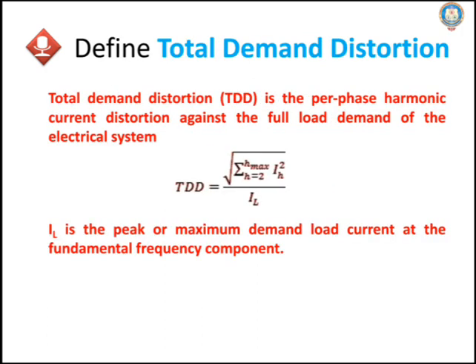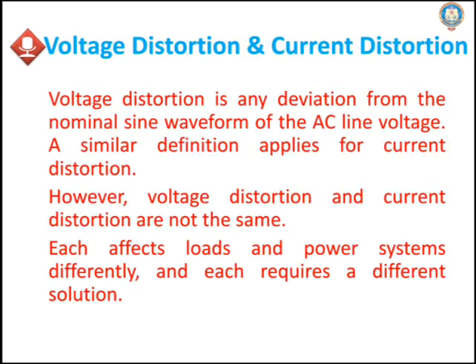Define Total Demand Distortion. Total Demand Distortion (TDD) is a per-phase harmonic current distortion against the full load demand of the electrical system. TDD = √(Σ from h=2 to h_max of Ih²) / IL, where IL is the peak or maximum demand load current at the fundamental frequency component.